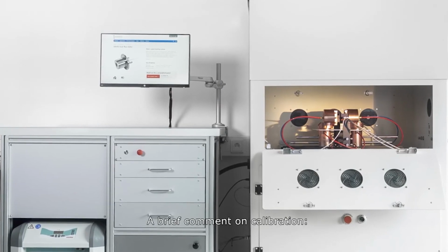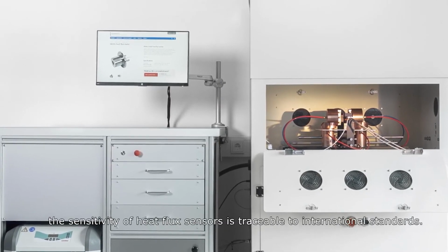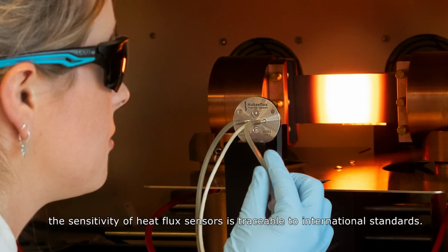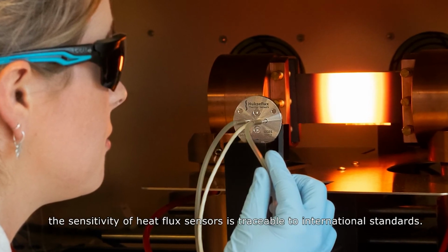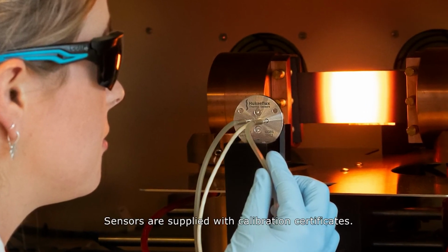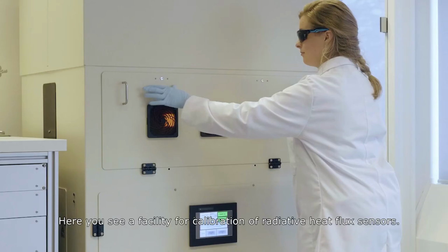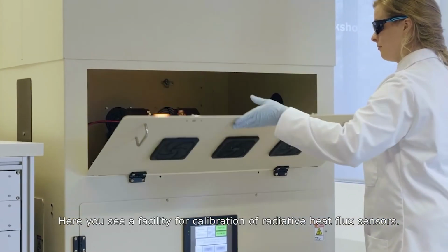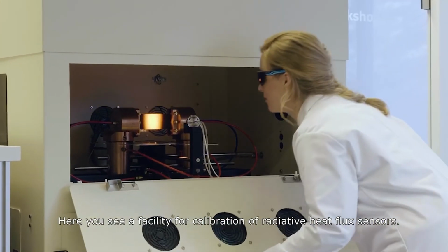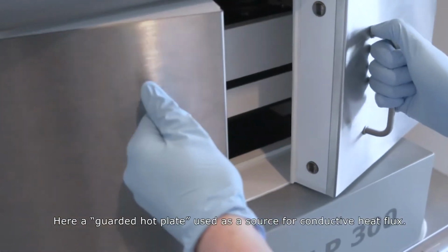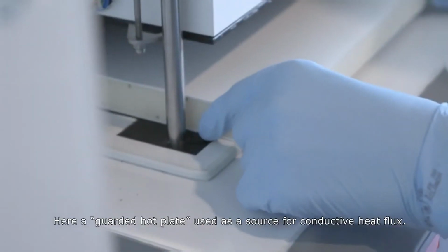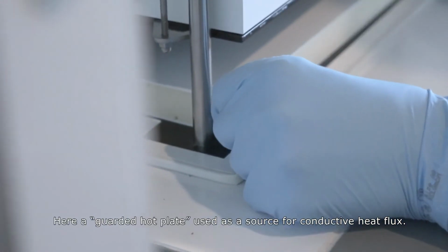A brief comment on calibration. The sensitivity of heat flux sensors is traceable to international standards. Sensors are supplied with calibration certificates. Here you see a facility for calibration of radiative heat flux sensors. Here, a guarded hot plate used as a source for conductive heat flux.